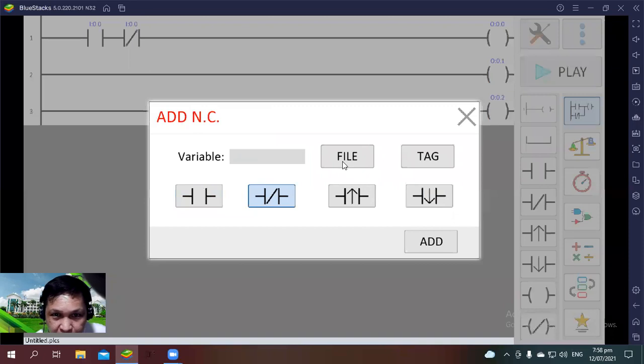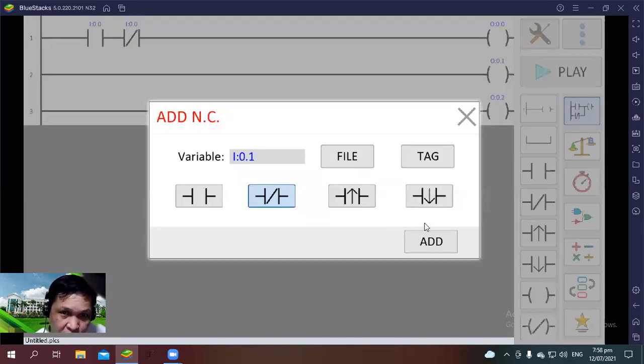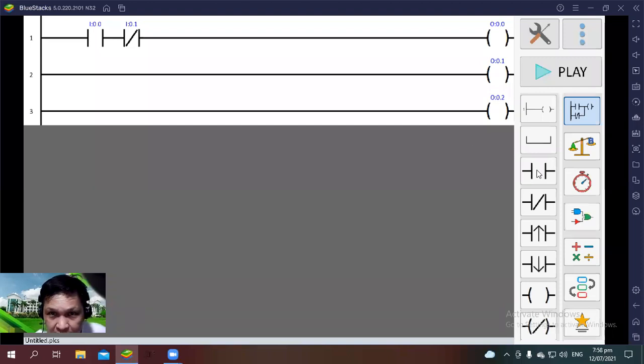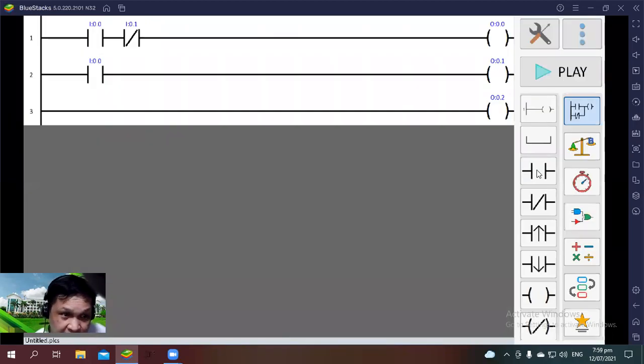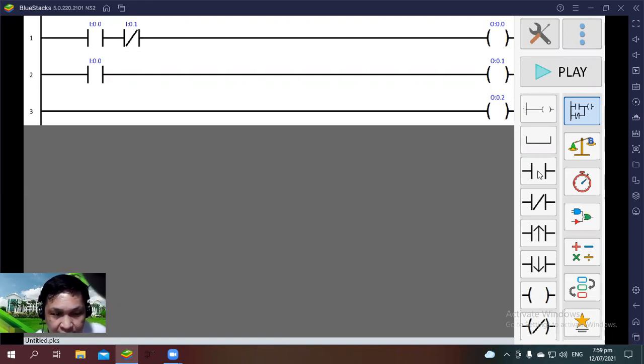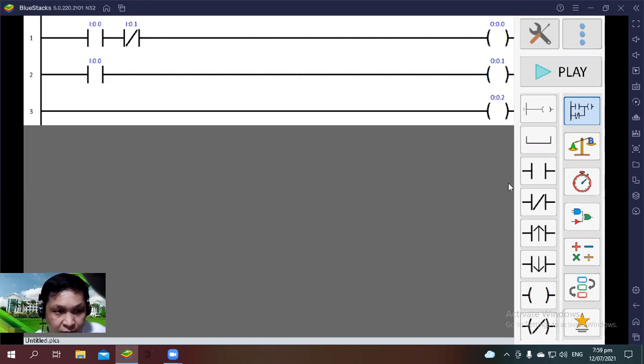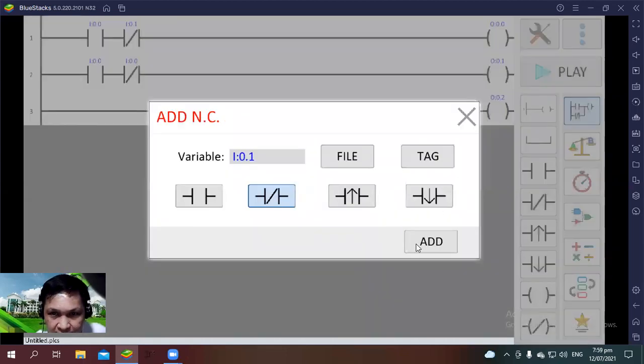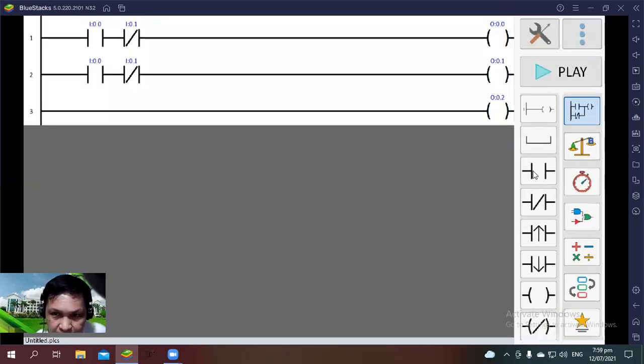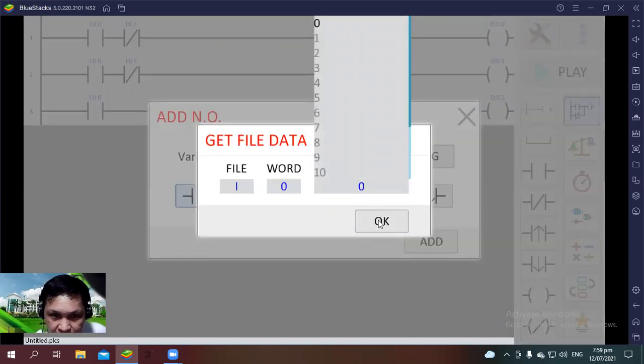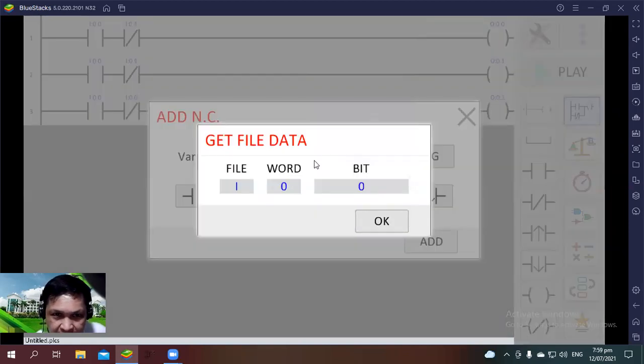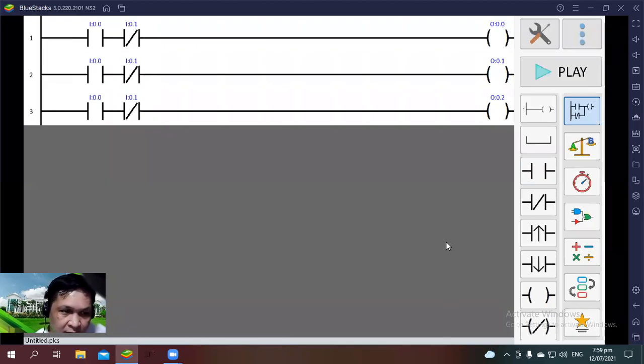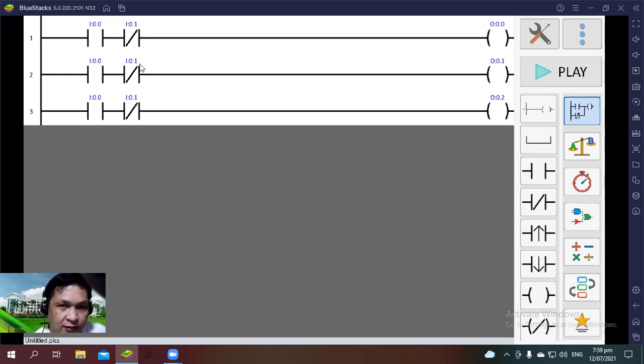Again, I always set my stop button to be at one, my start button to be at zero. All of the rungs must have the settings of the start and stop to ensure that any disabling of the start button or disabling of the stop button actually inhibits or stops the program from working. So let's add in one more and set it to one, and add in one more and let's set it to zero. Add in one more and set it to one. So for the most part, all PLC programs will probably have this safety feature.